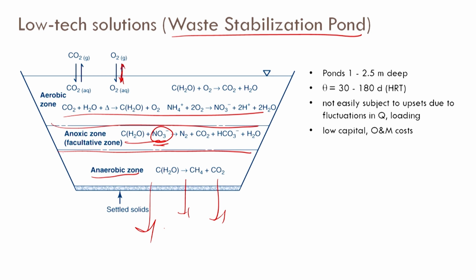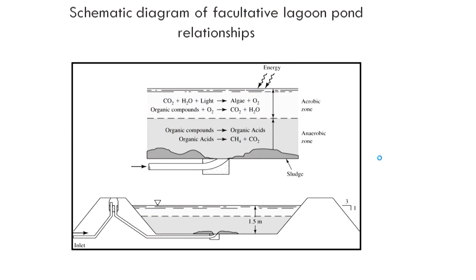It will not work that way, right. So, hydraulic retention time as we see here is 30 to 180 days or such. So, you can look at the area, and theta for SBR and such, let us say, is 4 hours or so, let us say for your SBR plant, 4 hours. So, that is something that you can consider.